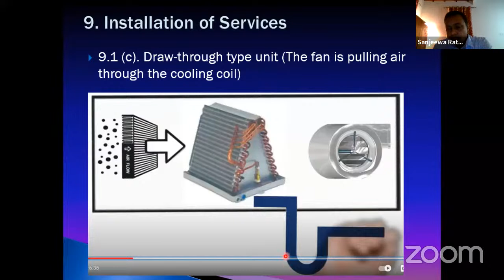If it is the other way, it's a blow-through. You can clearly identify here. See, this is a blow-through type configuration, whereas this is the draw-through type. We discussed the draw-through type one, where inside the coil there is a negative pressure, so more height is required for the U-trap. The first one here is very rare in construction for AHUs.